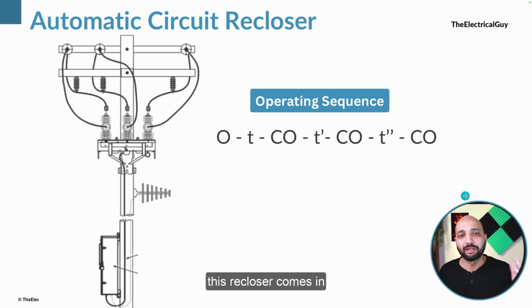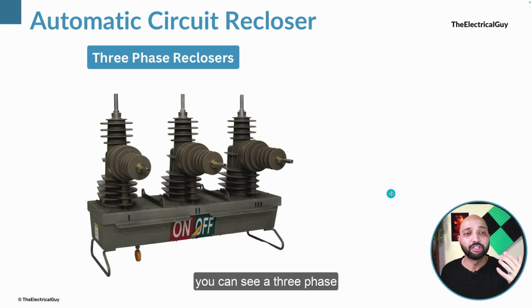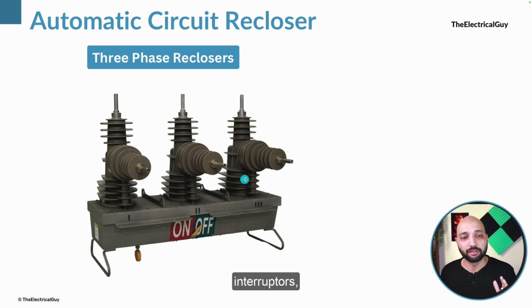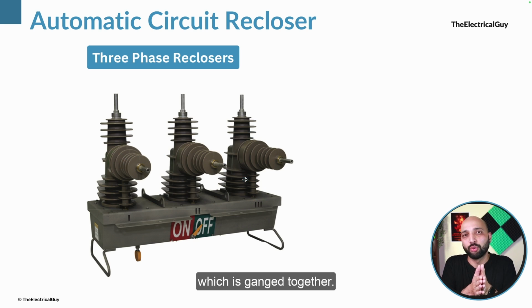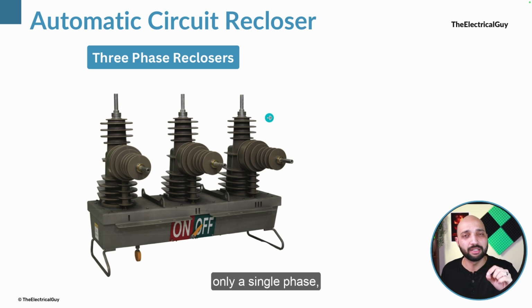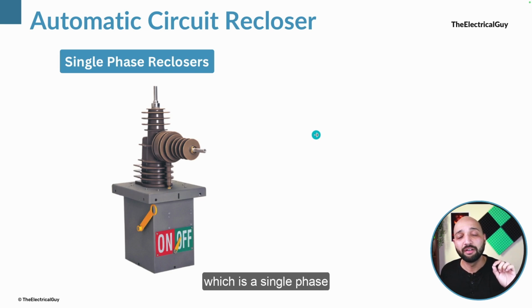Now this recloser comes in multiple options. You can see a 3-phase recloser like this. It will have 3 different interrupters, which are ganged together. This is also called mechanically ganged operation. That means if, let's say, a fault happens on only a single phase, all the three phases will trip and reclose accordingly.